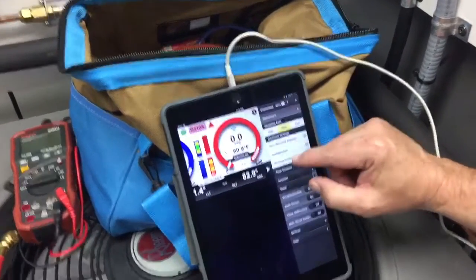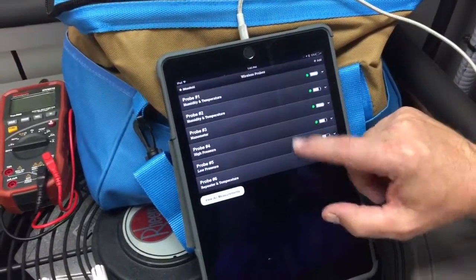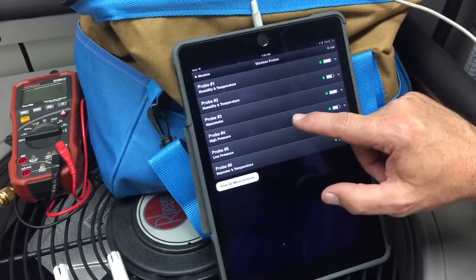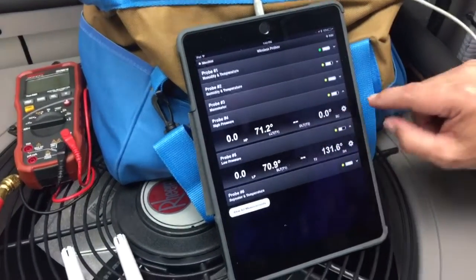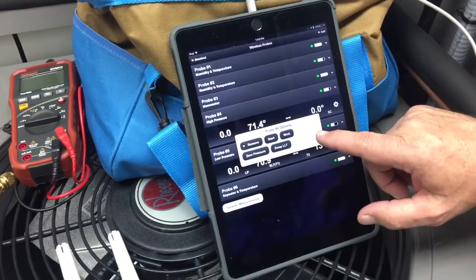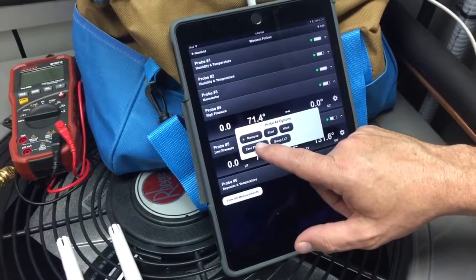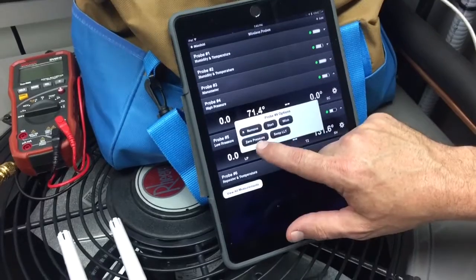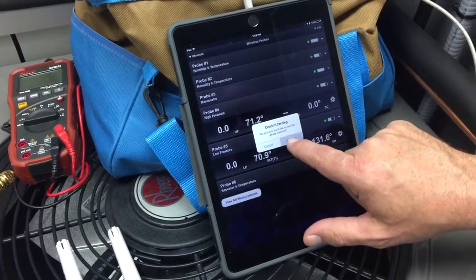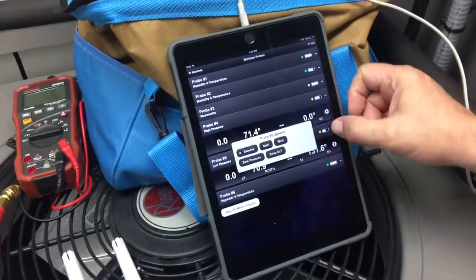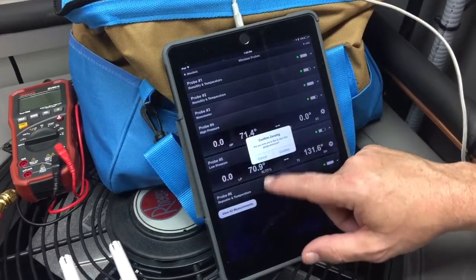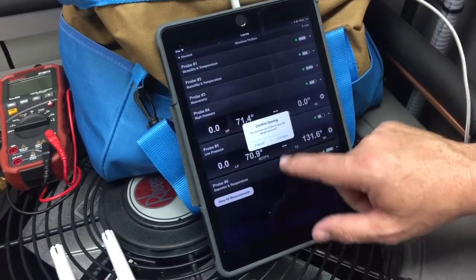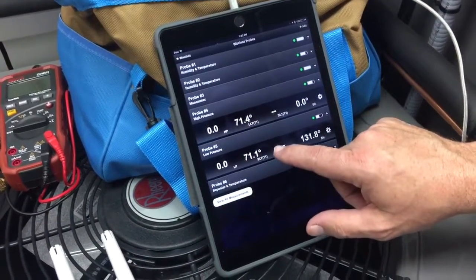Now another interesting thing you need to realize in the wireless probe menus: some probes like high pressure probes and low pressure probes have additional configuration options. So in this case here, we can tap on that gear and we can zero the pressures and hit confirm. That'll allow us to zero that pressure out. Same thing here with the high pressure probe. Zero it, confirm. That's going to allow that to hold a zero place.